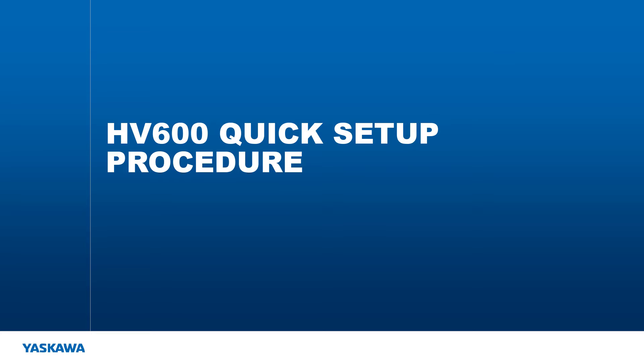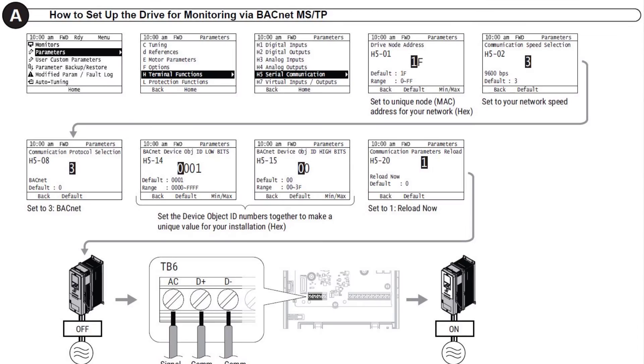Yaskawa has taken the steps to make connecting and communicating easy. Included with the HV600 product, you'll find a large fold-out quick setup procedure that makes the complicated simple. With easy-to-understand graphics, the procedure focuses on tasks all of our customers will perform with AC drives. In this ELM, we'll be focusing on additional procedure A: how to set up the drive for monitoring via BACnet MSTP.